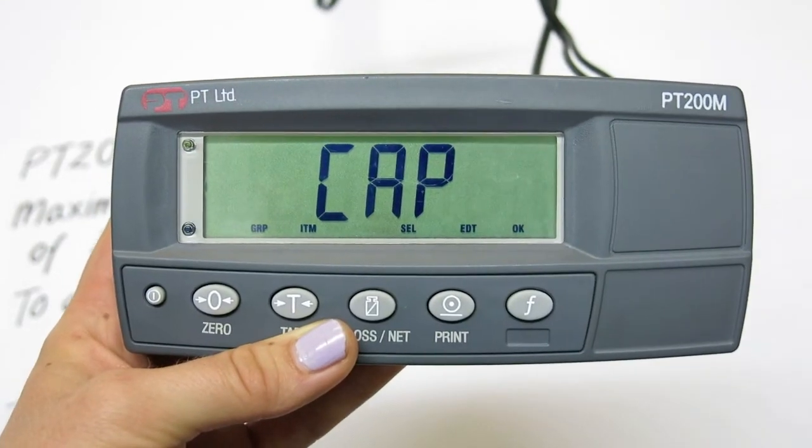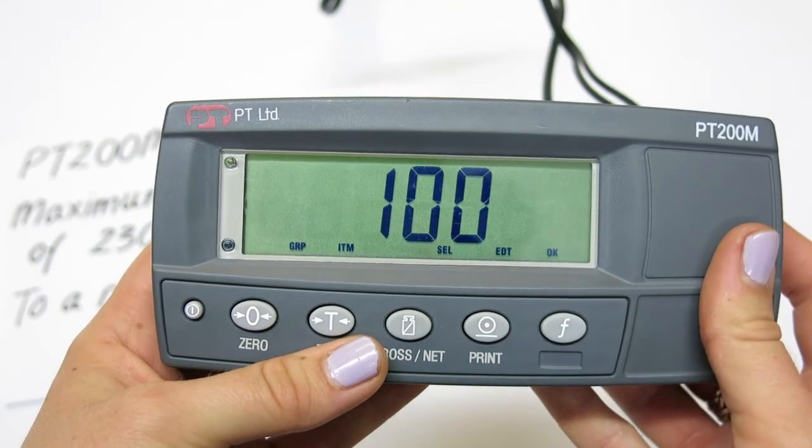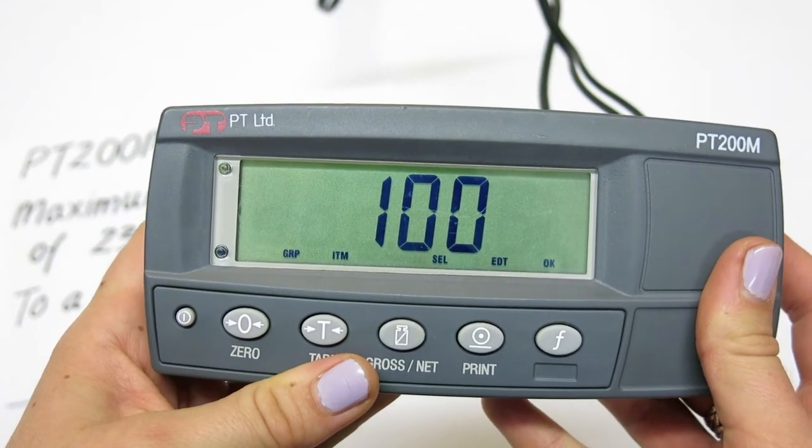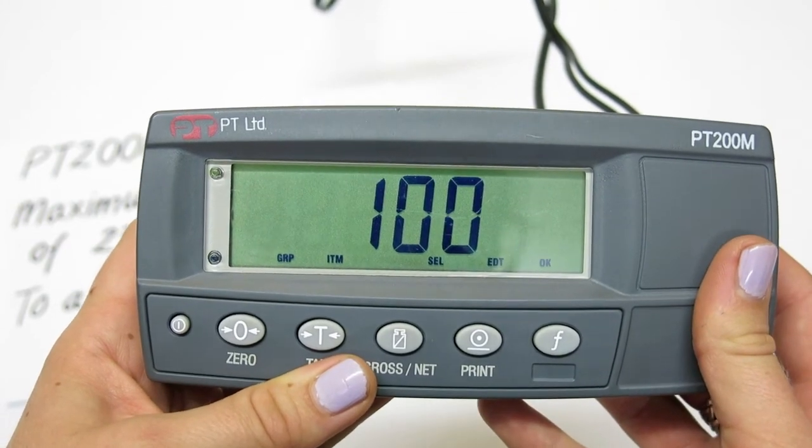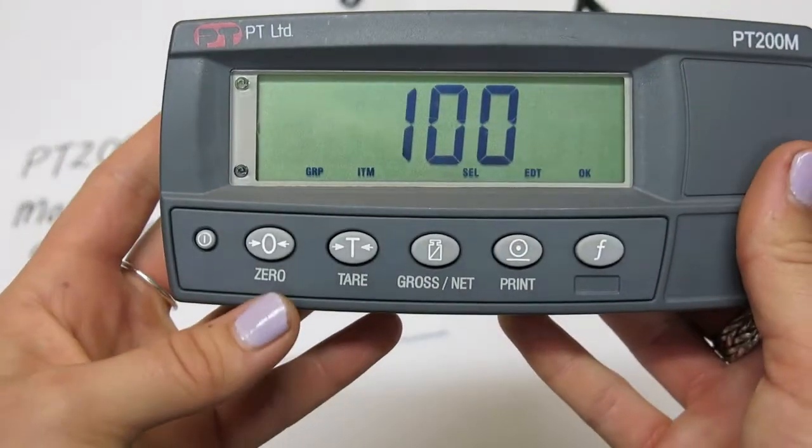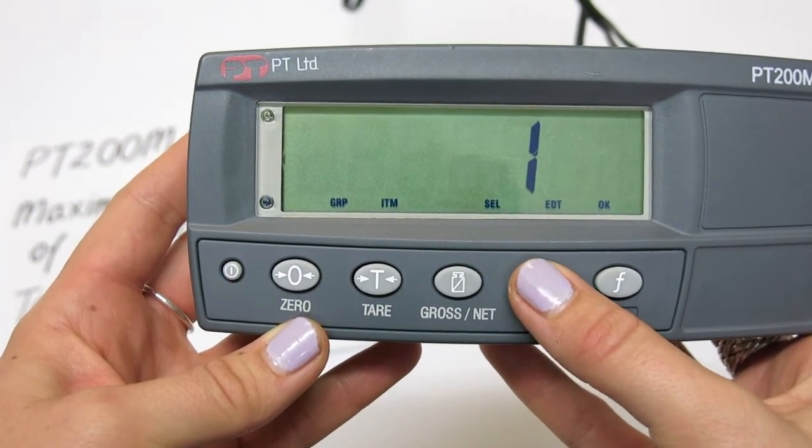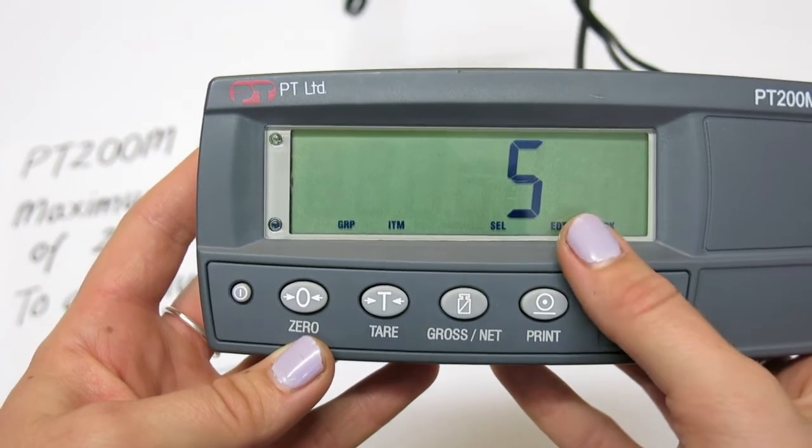The next parameter is resolution. This is the step number that the indicator counts by in the lowest digit of the value. So for our example, we want to count in steps of 5. Using edit to scroll and OK to select, find and accept 5 in the menu.